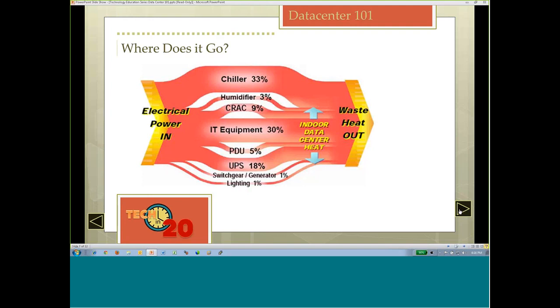Right in the middle gives you the answer. Only 30% of your total environment is IT equipment, and it may be a little more than that depending on it. You'll hear some industry numbers called PUE, power usage effectiveness, and data center infrastructure efficiency, DCIE. PUE is that efficiency number, meaning you're getting your compute power and your infrastructure power, the lower the number the better, so something like 1.08 is a very good PUE. That means you're not spending that much more on your non-computing equipment than on your computing equipment. Data centers will strive to get that number as low as they can. By the way, when we started CA, their number was well over 2 with their PUE. Now I think it's somewhere around 1.6, which is pretty good.